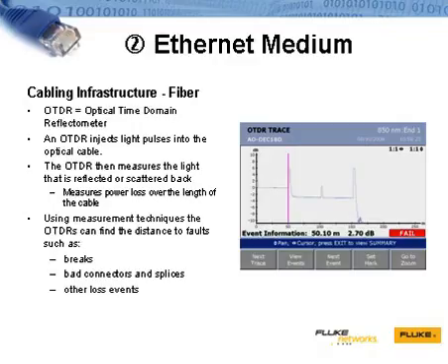Any reflections are recorded as reflective events and seen as spikes on the screen. OTDR traces provide performance details about the connectors, splices, or breaks along the fiber optic link. And this is true for any OTDR.